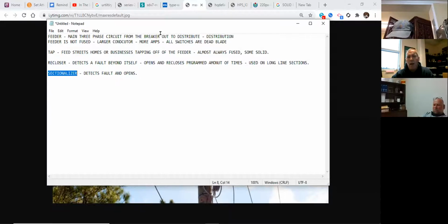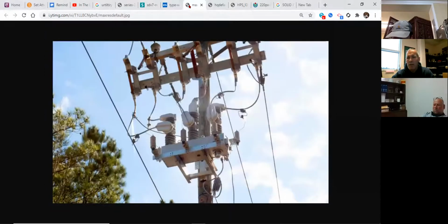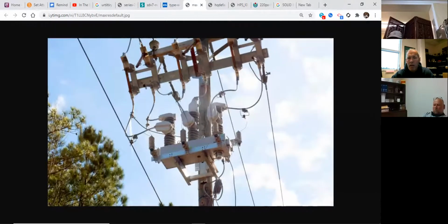I see a fault beyond myself. So let's go back to the picture. We'll say this is my inbound conductor, and these are all bypass switches right here. I've got my inbound going into the switch, and my outbound coming out of the switch. A fault occurs somewhere down this line, it detects it, it opens, and that is it, period. I want only one shot open, and that's all I want it to do.